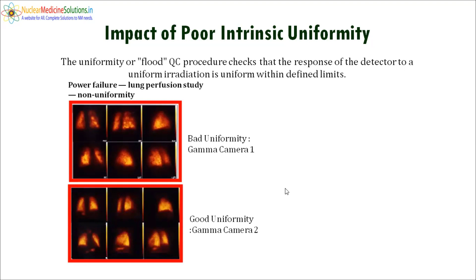This is a lung perfusion study performed on gamma camera 1, showing a patchy uptake in the image, which is not matching with the pathology of the patient. When the same patient was imaged on gamma camera 2, the image is perfectly okay. After investigation, it was found there was a bad PMT tuning. Because of this bad PMT tuning, we are getting this type of effect in the image.